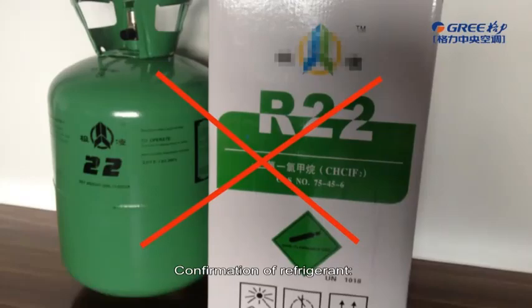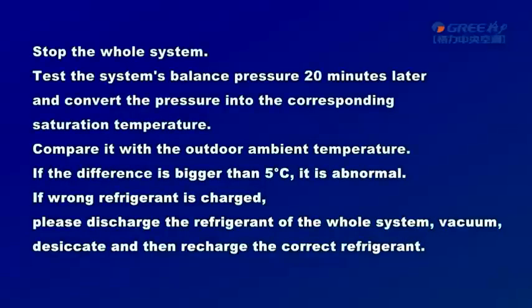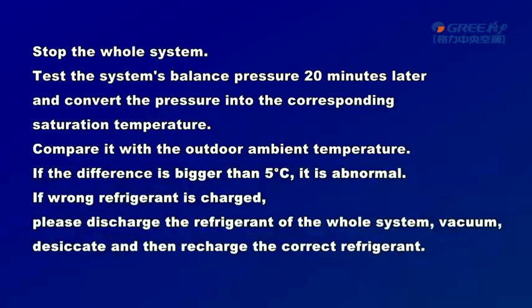Confirmation of Refrigerant: Stop the whole system, test the system's balance pressure 20 minutes later, and convert the pressure into the corresponding saturation temperature. Compare it with the outdoor ambient temperature. If the difference is bigger than 5°C, it is abnormal. If wrong refrigerant is charged, please discharge the refrigerant of the whole system, vacuum, desiccate, and then recharge the correct refrigerant.